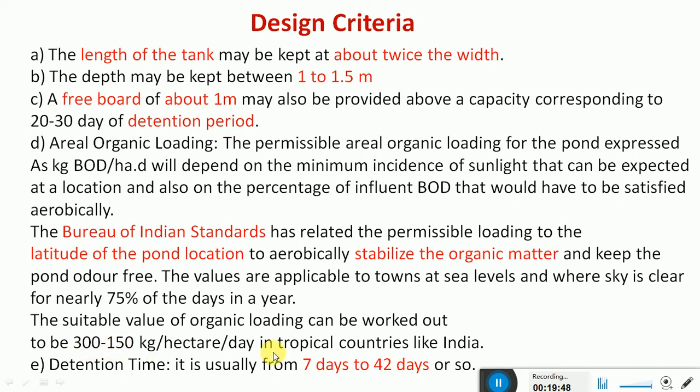And the detention time usually varies from 7 days to 45 days or so. So there is a wide range. The 7 days corresponds to the oxidation ponds to which we supply the oxygen externally. The 45 days, or up to 1 month, are for the natural ones, where we do not supply any oxygen. So that's why the detention time varies depending upon the type of the tank.